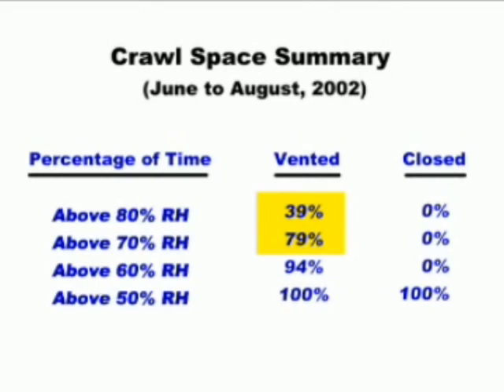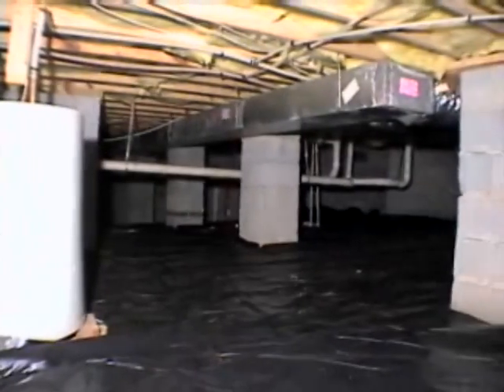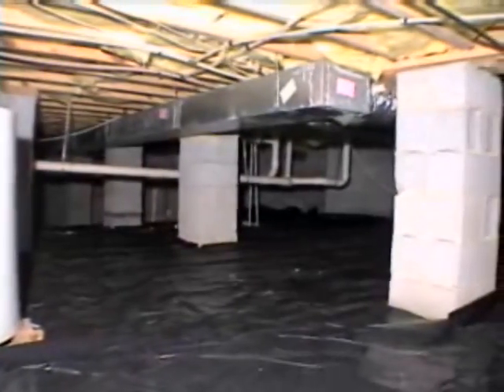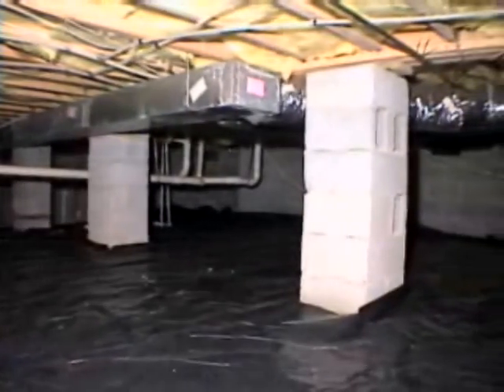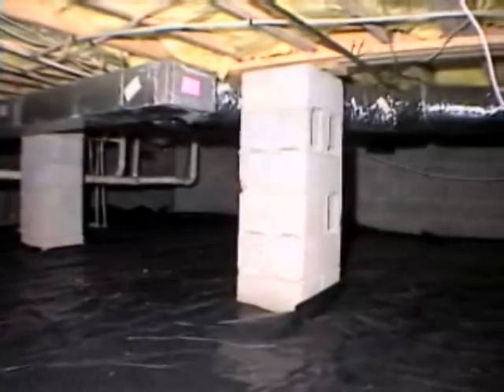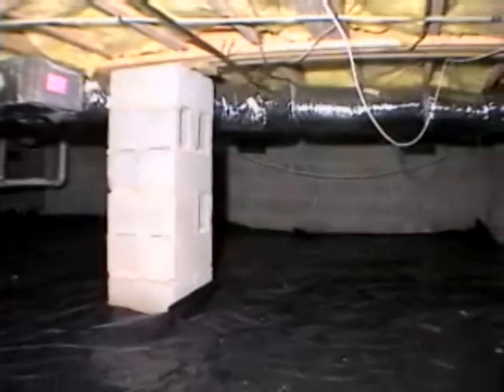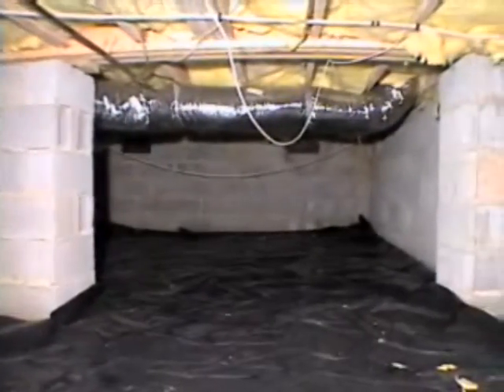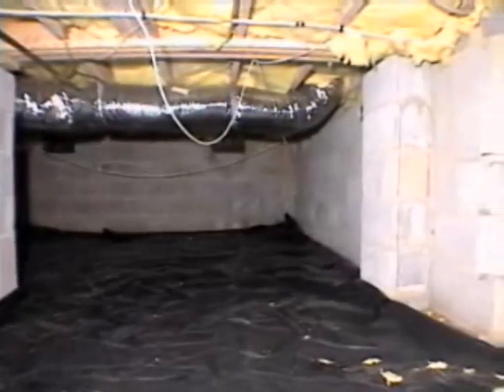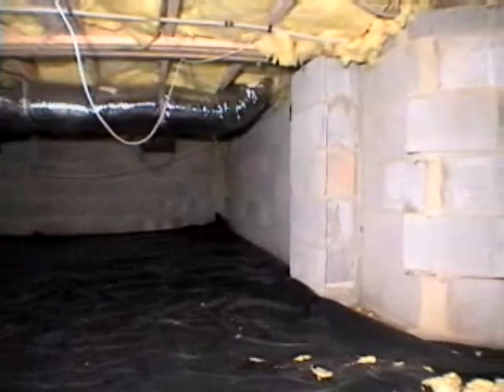To effectively prevent mold blooms, crawlspace moisture levels should be kept below 70% relative humidity. These results also bring into question the effectiveness of ground vapor retarders in controlling crawlspace mold. Many building professionals have thought that a full coverage layer of 6-mil poly on the ground was the main strategy needed to control crawlspace moisture. The field test results do not support this belief when it comes to mold prevention. Despite the carefully installed 100% coverage ground poly, excess moisture continues to enter and remain in the wall-vented crawlspaces, creating a damp, mold-friendly climate in humid weather conditions.